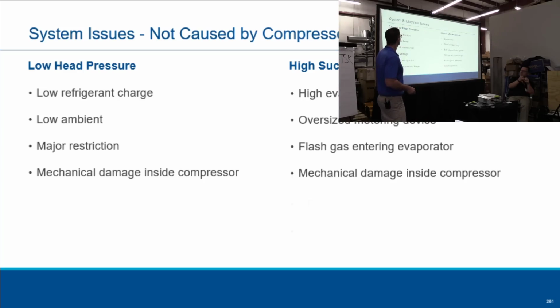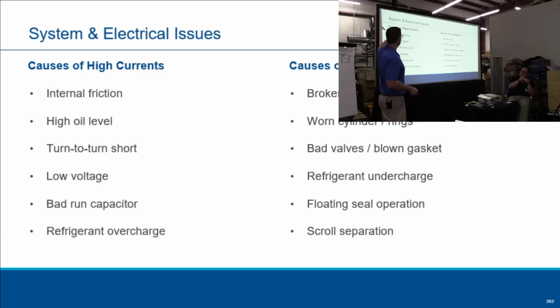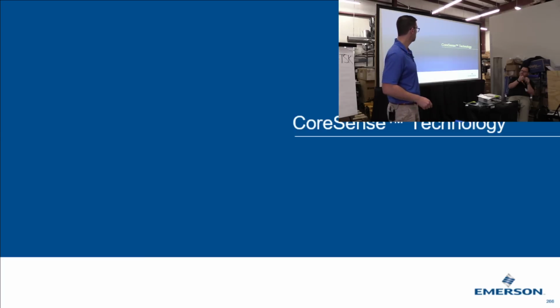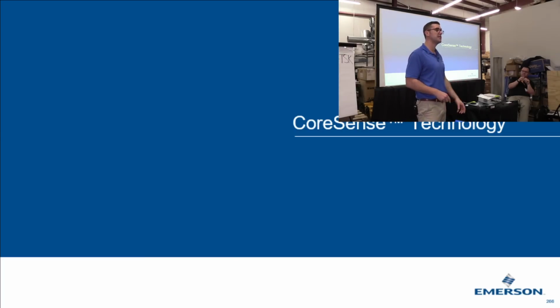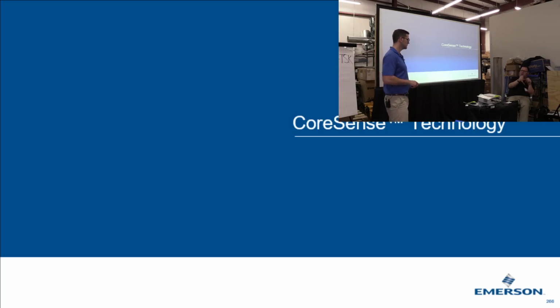So, system electrical issue, internal friction, high oil, turn-to-turn short, low voltage. Causes of low current: broken rods, worn cylinders, bad valves. We talked about all this stuff. Okay? I'm going to go quickly through the CoreSense technology, then we're going to get the compressors out here, and then we're going to have some people tear some of these down, okay? We'll take a break just after we go through this section. Almost at lunch, 11:34.